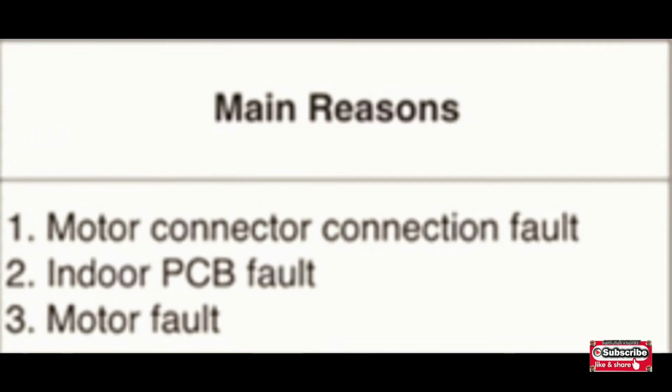Main reasons of this error: number one is motor connector connection fault. Maybe your connection is not good. Indoor PCB fault, maybe your PCB is faulty. And motor fault, maybe your motor has a problem. So you must check these three problems. First you can check the motor connector, whether your connection is okay. Then the indoor PCB, maybe your indoor PCB is faulty. You must check your indoor PCB and motor, and at the end you can check your motor.